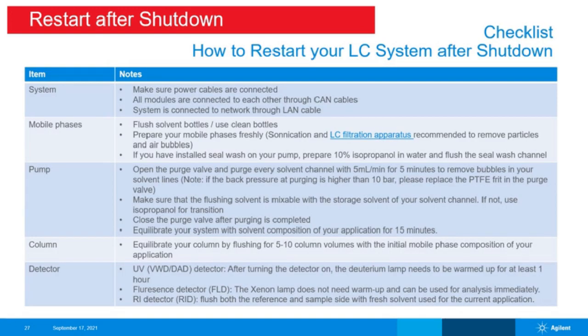In the table below, you have some details on that step-by-step approach and a checklist of things to do or to verify. It's very important to have a segmented approach and address first all topics related to the system itself. Then think about the mobile phase, then the pump, then the column, and finally the detector.